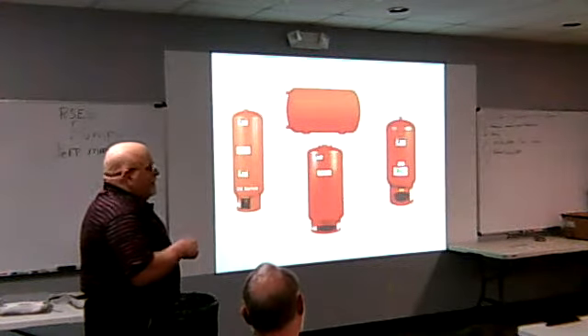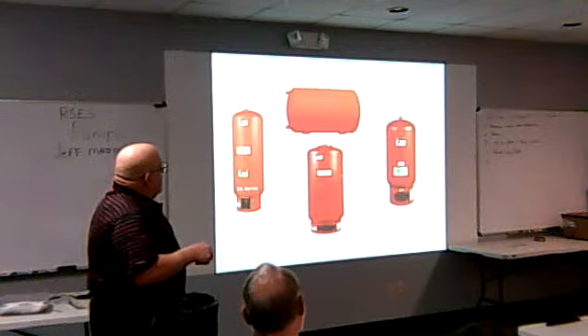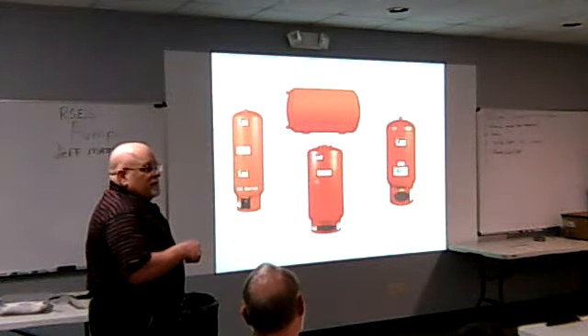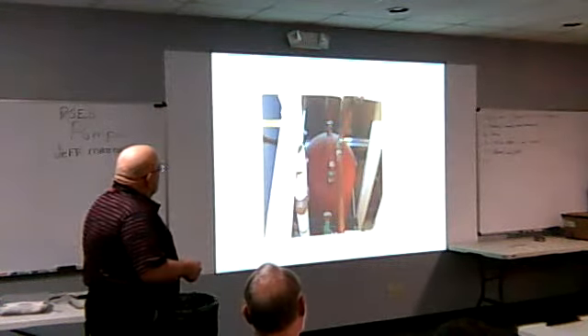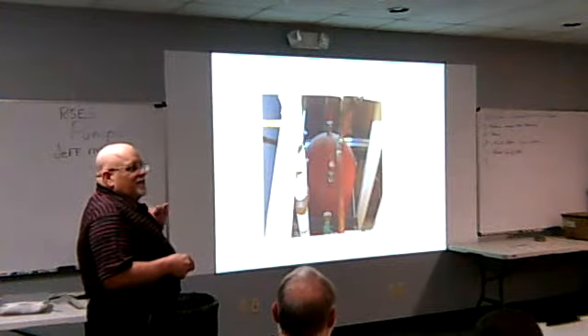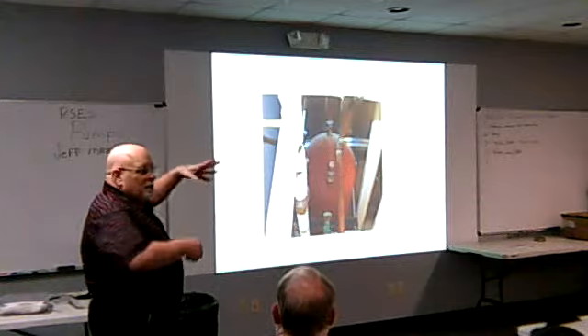This is a CX series. This is a diaphragm tank, and these are a bladder tank and a full bladder tank. I'll go through it. You see the bladder here. Here's your gauge glass. It's okay for it to be half full. It's never going to be empty because if I have 20 pounds of fill on it, 14 pounds of air in there, it's going to have compression. That's why it's called a compression tank.